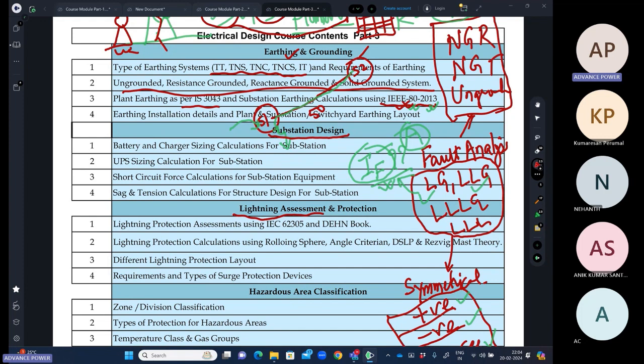We'll do the lightning assessment, and in detail we'll see IEC 62305, and one famous book you might know, the DEHN book, a German book which is a pioneer in lightning equipment manufacturing. There we will first assess whether lightning protection is really required or not. We determine the LPL 1, 2, 3, 4 according to the system, and if it is required, we check with which method we should protect: rolling sphere, angle criterion, or, in substations, the most famous, the Rejvig method. The Rejvig method has a mast theory, so for lightning we use the lightning mast. Through masts we protect the substation, along with the shield wire which runs through the tower peak.